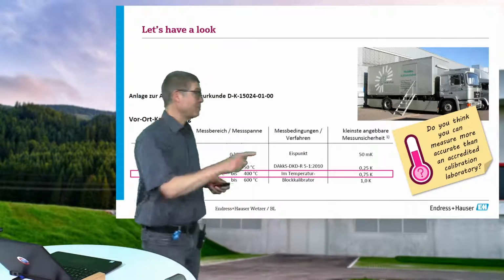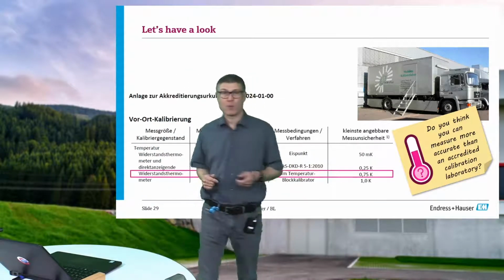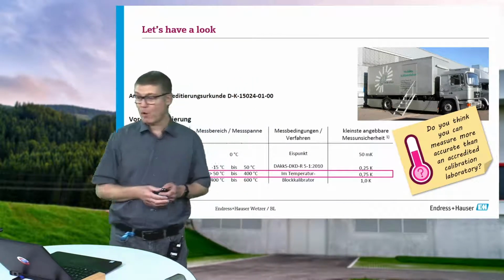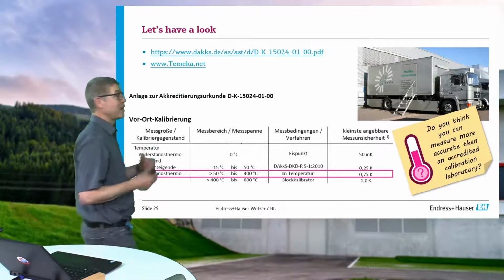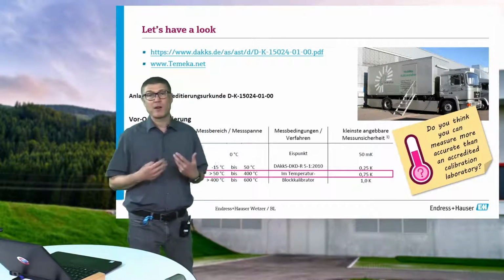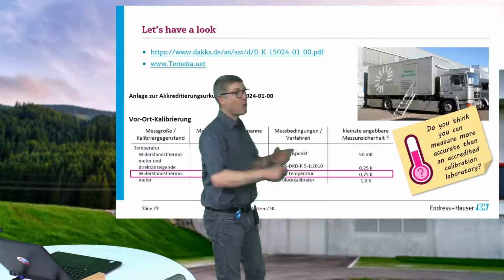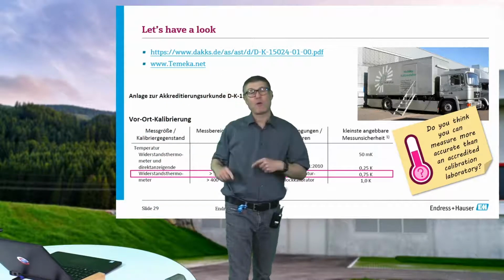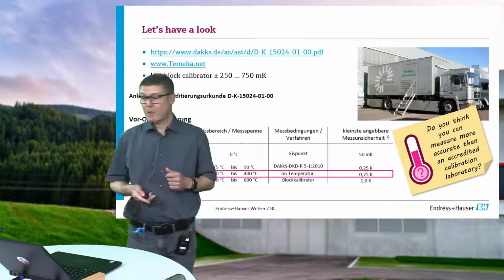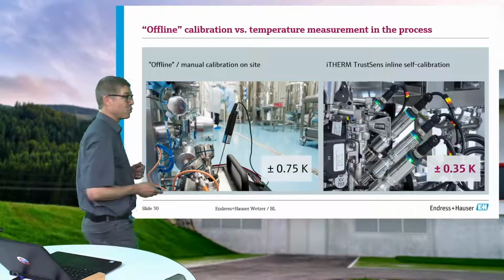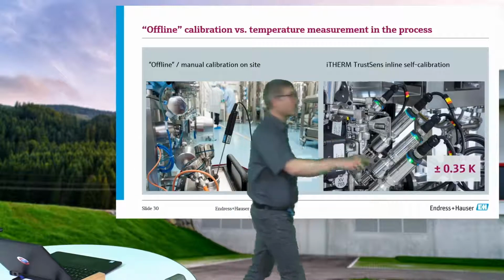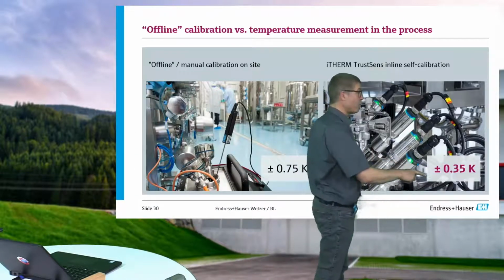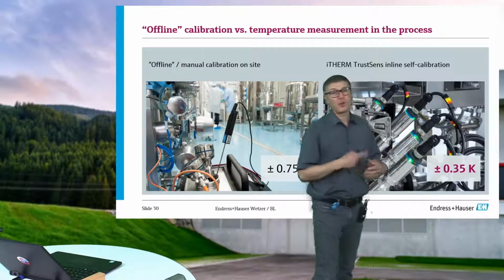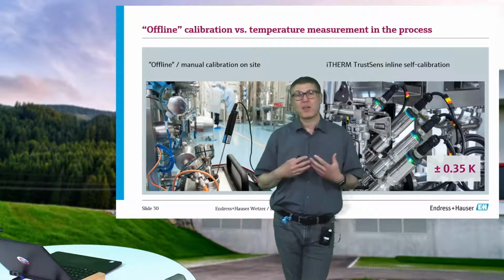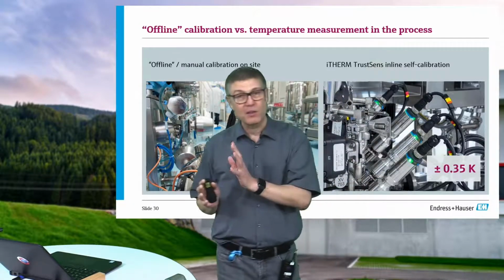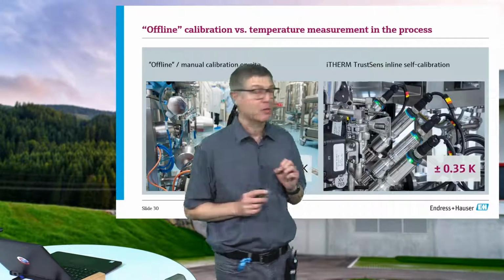So you should also work with this if you're using a dry block calibrator. That means if you're doing your 3-point calibration, all of these points have an uncertainty of this value. And let's see what the TrustSens can do.